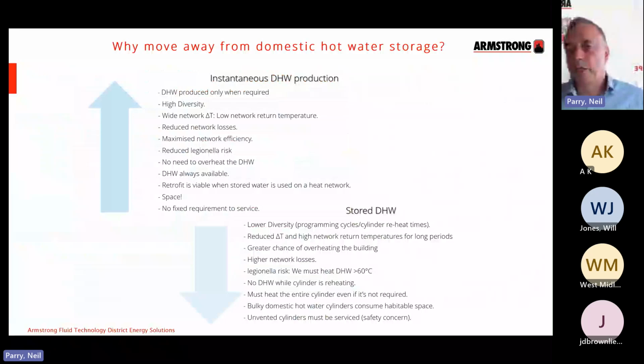But as we've started to look at heat pump only networks where the flow temperature has been reduced to maybe 55 degrees, we've started to think, I need to think about storing hot water here because I haven't got enough energy in the primary side to give me instantaneous production, and at least if I store it I can put an element in there, an electrical element, and use that to raise the hot water temperature.